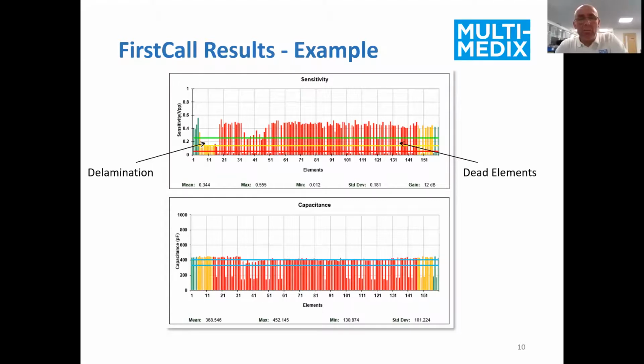Moving along to the other side, and we can see multiple examples of this across this report, we've got some dead elements where we've entirely lost the sensitivity performance. So we've got no acoustic transmit and receive, and that's because we've got dead elements, because I can see below that we've got a level of sensitivity that remains on this particular probe. So that tells me a lot. Rather than just saying I've got a defective probe, I can now say I've got a defective probe for certain reasons, and that can help us either with repair options or even understanding whether there's been problems with good care and use by the sonographers and the users.